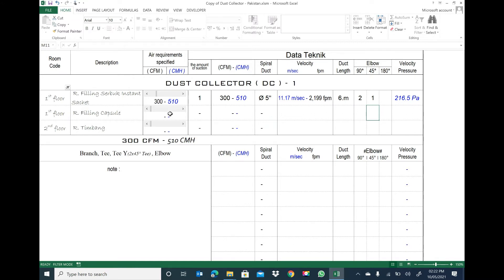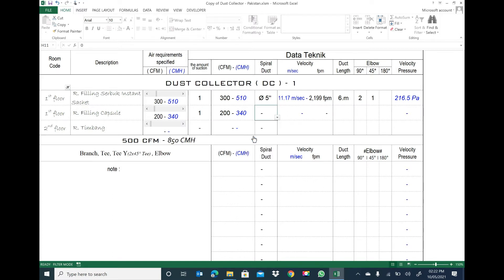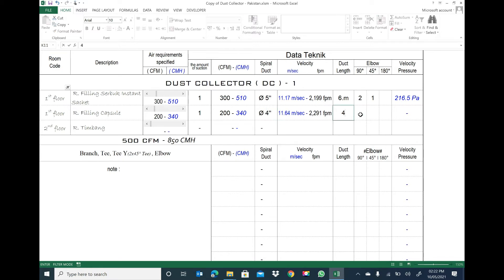We go to the next clean room. Same way, we see the airflow — how much we need to exhaust. This is the capsule filling area. There is also one suction grill. We check the duct size: at 3-inch the velocity is 20 meters per second, which is too high, so we go to 4-inch. Suppose this duct is 4 meters with one elbow at 45 degrees. The pressure losses and velocity pressure are calculated automatically.